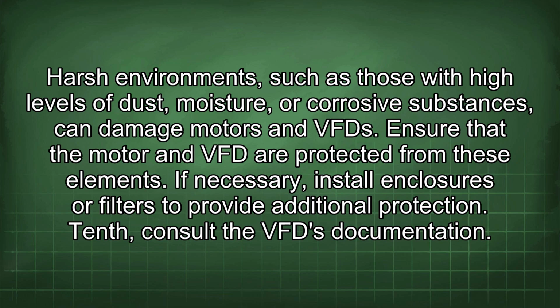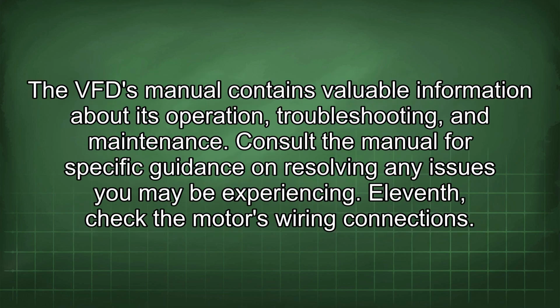Harsh environments, such as those with high levels of dust, moisture, or corrosive substances, can damage motors and VFD. Ensure that the motor and VFD are protected from these elements. If necessary, install enclosures or filters to provide additional protection. 10th, consult the VFD documentation. The VFD manual contains valuable information about its operation, troubleshooting, and maintenance. Consult the manual for specific guidance on resolving any issues you may be experiencing.